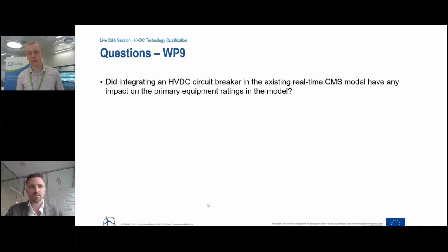So we did monitor the peak current in the circuit breaker and the energy dissipation in the circuit breaker, but it wasn't really the focus of our study, which is more a system level study. When we did the protection system design, we chose, for example, inductors in series with the circuit breakers so that the circuit breaker never exceeded its maximum fault current. So although we used the circuit breaker key performance indicators to evaluate that we didn't exceed the capabilities of the circuit breaker, because we did a good protection system design, this was just a verification, and we never exceeded the capabilities of the circuit breaker.